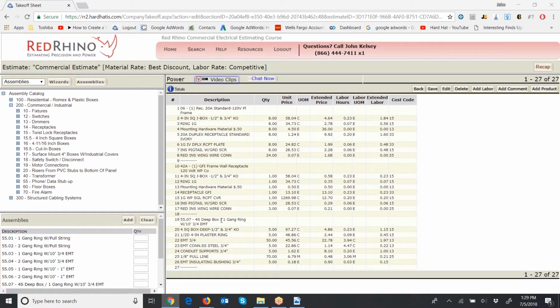It shows the description of the assembly here. Line 20 shows a 4S deep box with certain size knockouts. We input 5 assemblies, so there's 5 of those: 5 plaster rings, 50 feet of 3/4 inch EMT, set screw connector for the box, conduit supports, 70 feet of 1/8 inch pull line. See, it put a pull string in there for you, and it also put an insulated bushing on the side that stubs out. These are slick assemblies. When you get used to using these, you'll fly through the input of them.